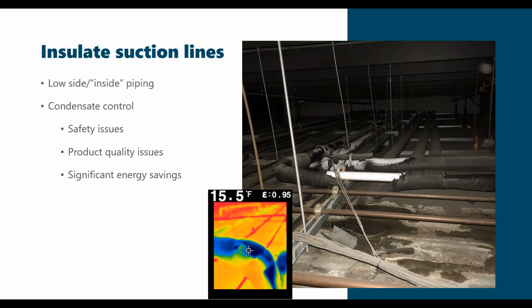The higher your delta T is of that refrigerant to the ambient temperature, the more energy savings there are with insulation. Same thing works with steam lines and any sort of thing where you're moving a liquid or gas that's at a much higher or much lower temperature than ambient conditions. Insulation always makes sense.